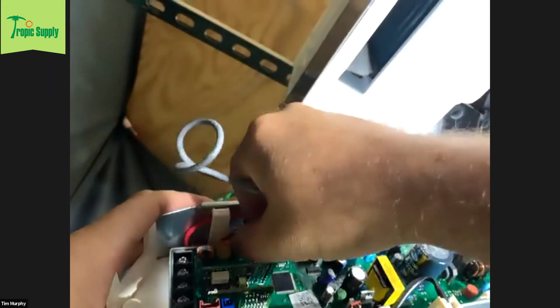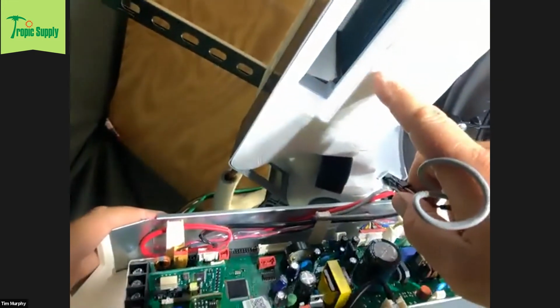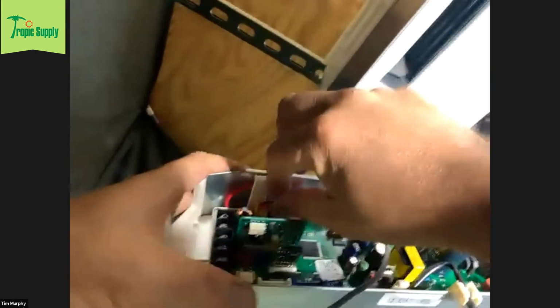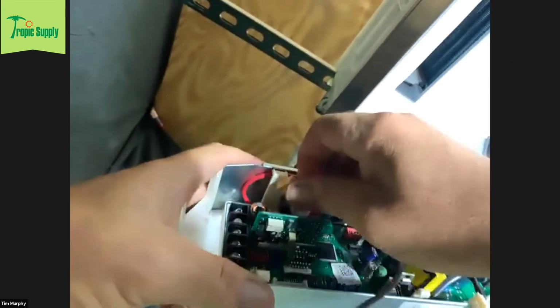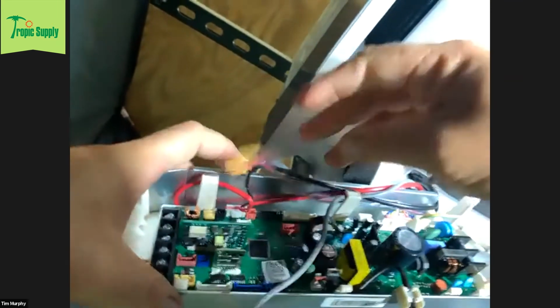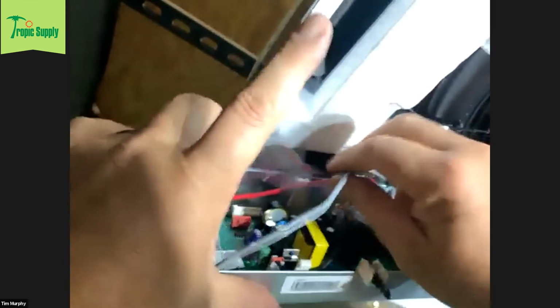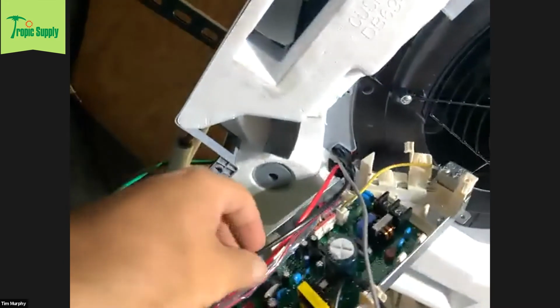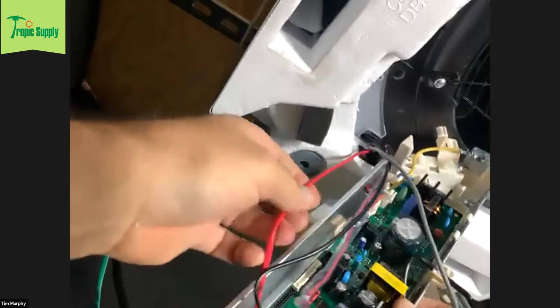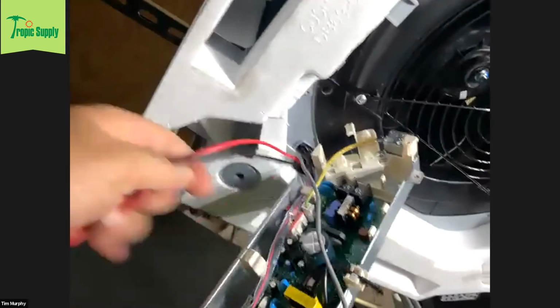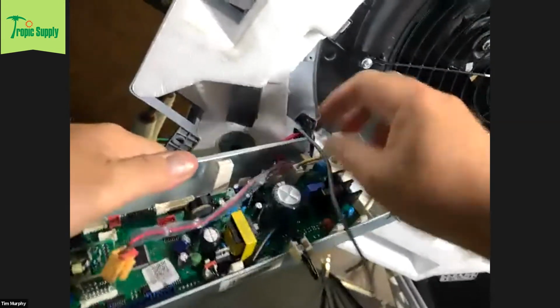You have your wiring here, and you're going to have all your overflow safety switch wire. There's like a little float sensor in this pan as well. That's going to trigger an error code. I believe it's the E153. That's going to let you know that the drain pan's full, and this is probably going to be your best bet to address that error code: go ahead and pull the drain pan, make sure that you do not have a clogged drain line or a bunch of gunk in this drain pan. You'll see once I pull it out, it's really not too hard to gain access to.